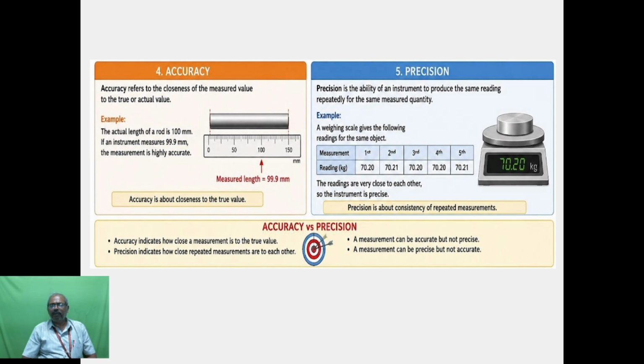Precision is the ability of an instrument to produce the same reading repeatedly for the same measured quantity. Example, a weighing scale gives the following readings for the same object. In the first attempt, it gives 70.20, second 70.21, third 70.20, fourth 70.20, fifth one 70.21. So the readings are very close to each other, so the instrument is precise. So the precision is about consistency of repeated measurements.